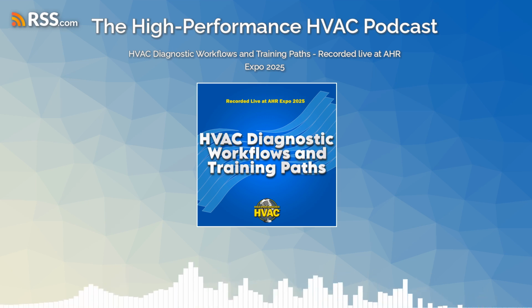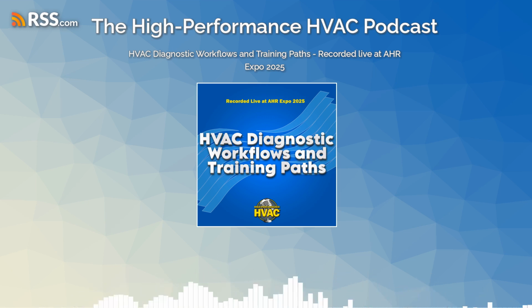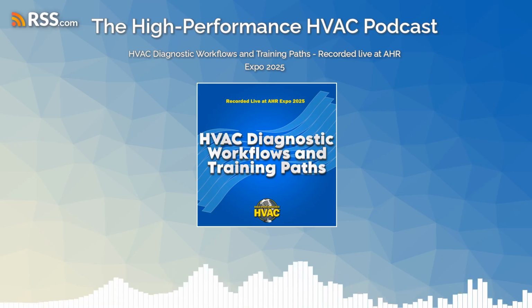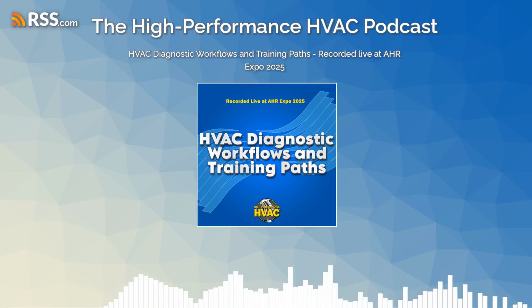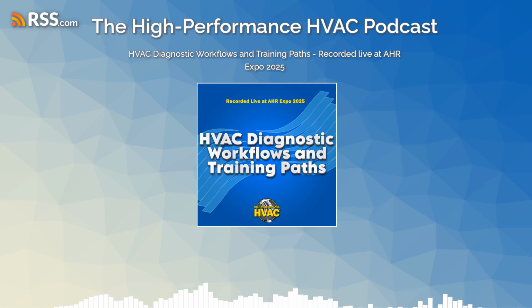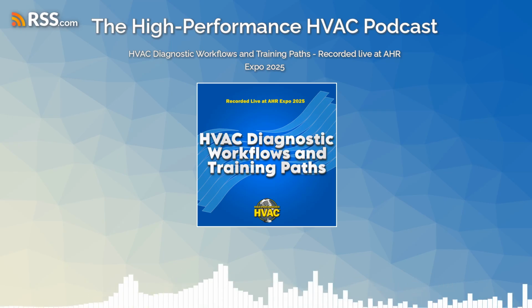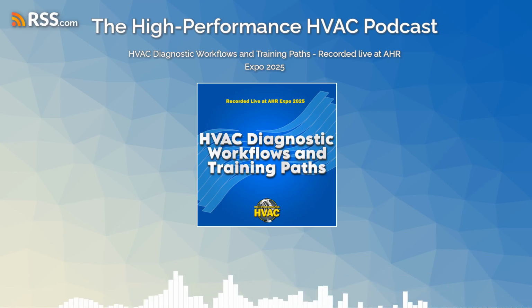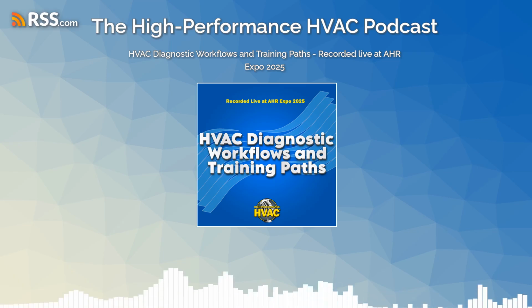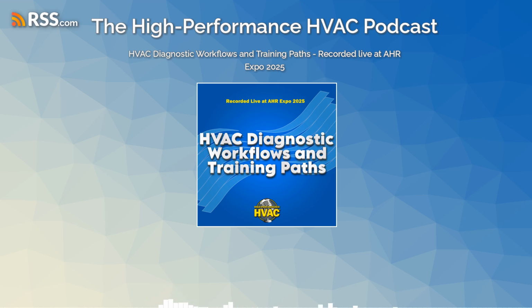I want to say one more thing about using the Trueflow as a sales tool. We talked about several ways to estimate or measure airflow, but particularly in a system replacement situation, what are the odds that the currently installed system—maybe the blower is the only thing that works—has a clean blower wheel, a clean evaporator coil, and a clean secondary heat exchanger? Because if you don't know if those things are clean, that fan chart isn't any good.